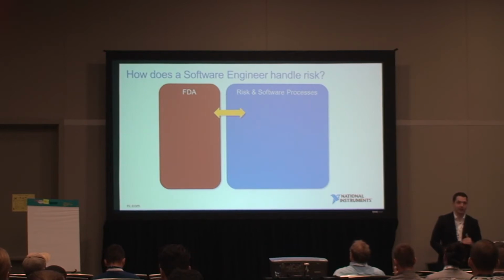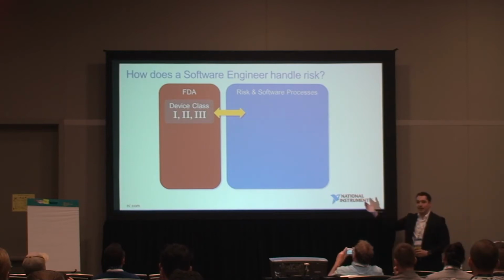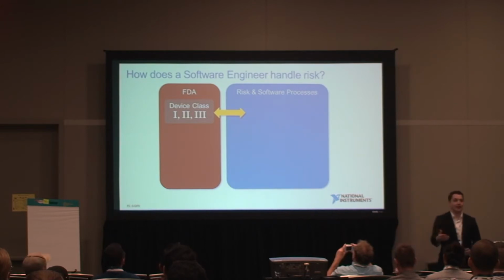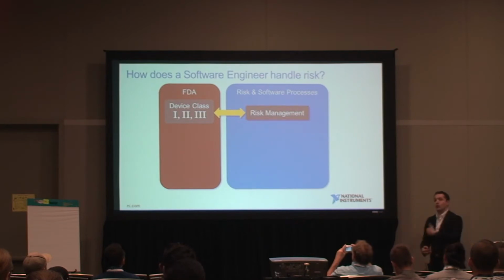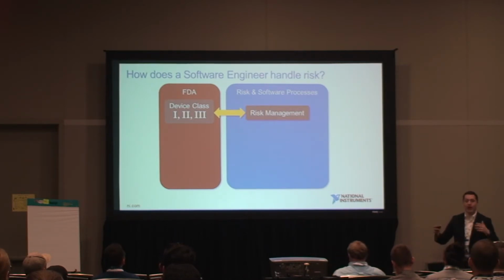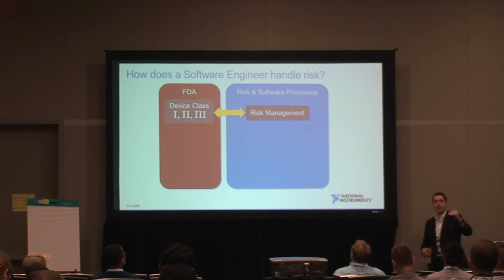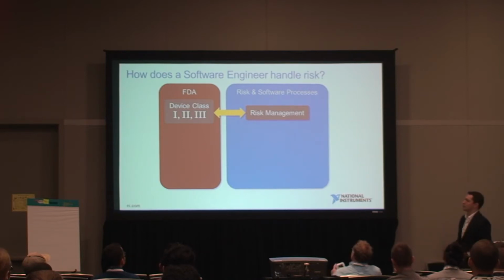There's a lot of little details, but here's kind of the stuff that a software person cares about. The FDA classifies the device. There's kind of a big lookup table where you can go find what an intended design might be, like an infusion pump or something like that. Then you do your own risk management based on that, based on your known hazards and harms. So you go through your design and step through it from system level all the way down to software, doing your FMEA in an iterative process. And then you have software process as well, like design reviews, like configuration management, that kind of stuff, which I'll briefly speak to in a little bit.